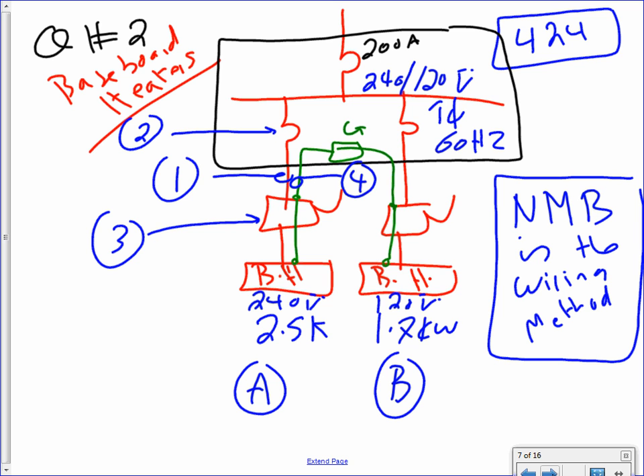When you say in the electrical design industry, a panel has to have a voltage, has to have an amp rating, has to have a frequency, and has to have a phase. Is it single phase or 3-phase? Now we're talking. Does that make sense, guys? It's not enough because this panel could be 480, 277, 208, 120, 240, 50 hertz, could be 3-phase, could be single phase, could be 2-phase even. So very, very important, guys, to get into the habit of identifying what you want. Ultimately, you're sending this to the electricians, and the electrical contractor is not going to sit there and guess what you want.